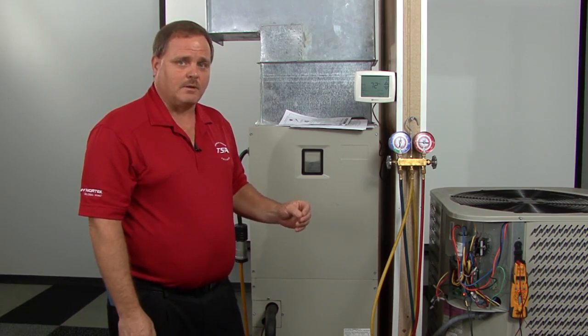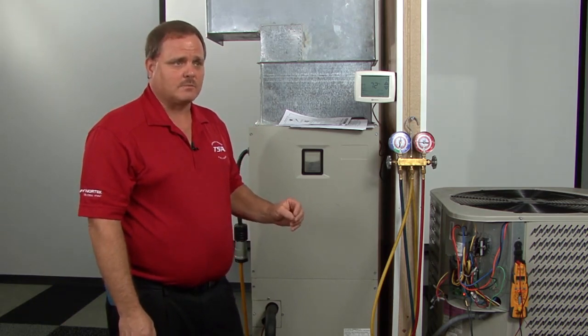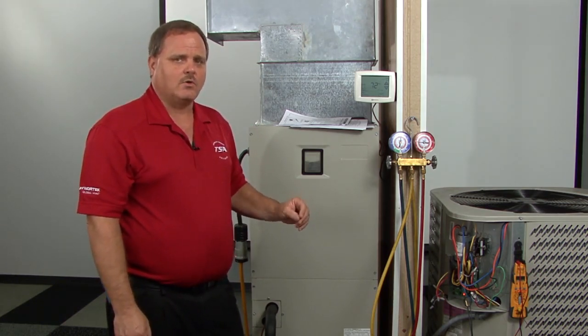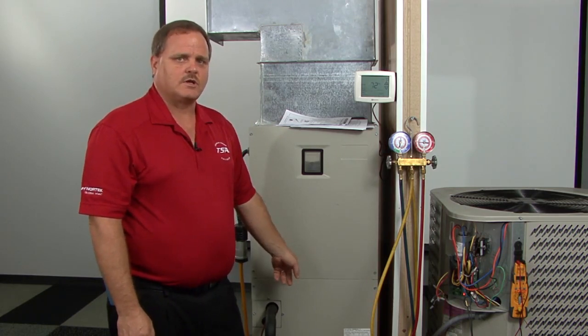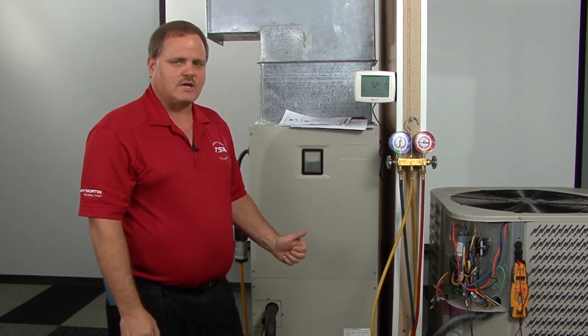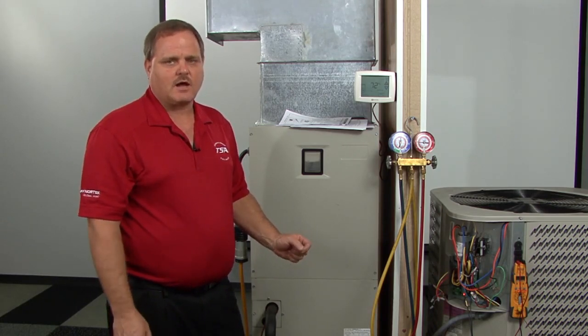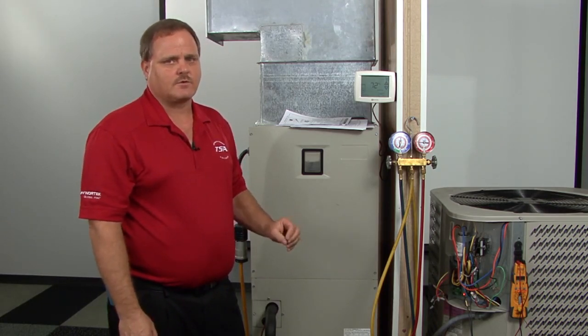Because airflow of the heat pump system is absolutely critical. Because remember, when you go into heating mode, that indoor coil becomes your condenser. So if we don't get that heat off that coil, that head pressure is going to skyrocket and you're liable to end up tripping out on a high pressure switch. So airflow is absolutely critical.